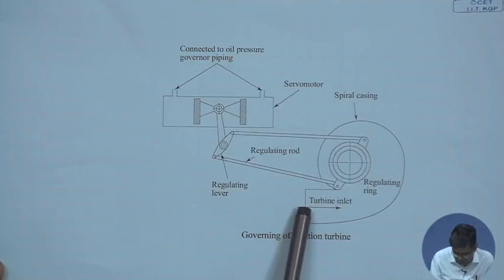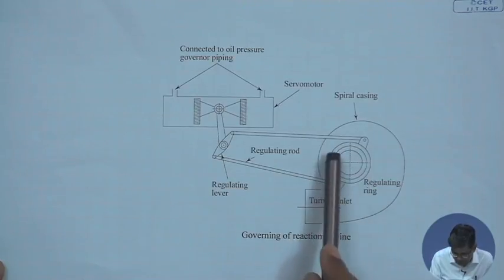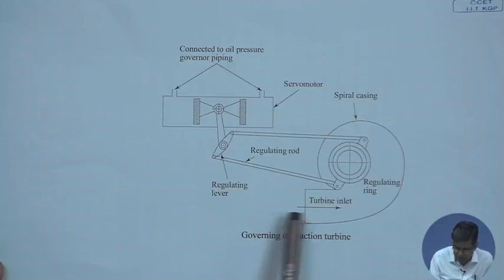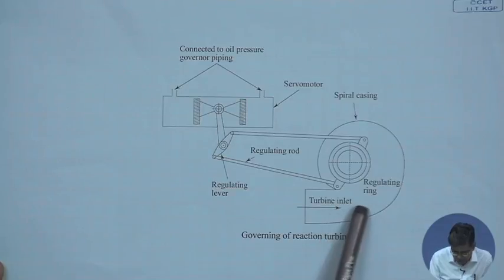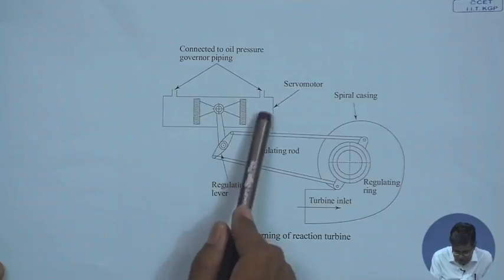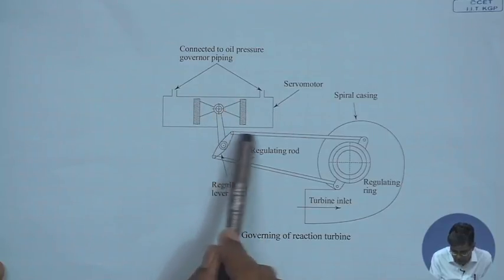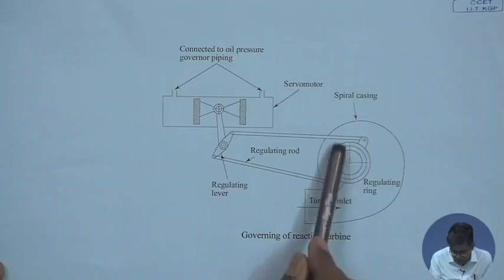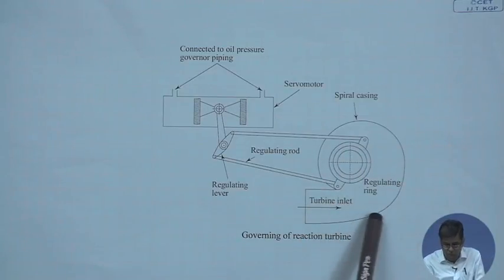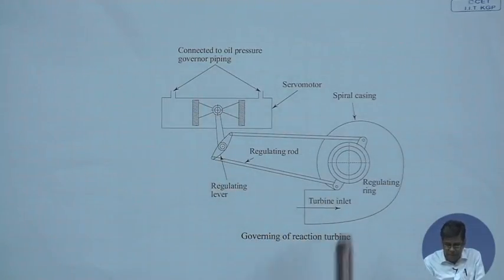The mass flow rate through the scroll casing remains the same overall, but when the system demands an altered mass flow rate — reduced when the load is reduced, increased when the load is increased — this is controlled through actuation of the oil pressure governor, via the lever, regulating rod, and regulating ring. This is how the control of all reaction machines is done.